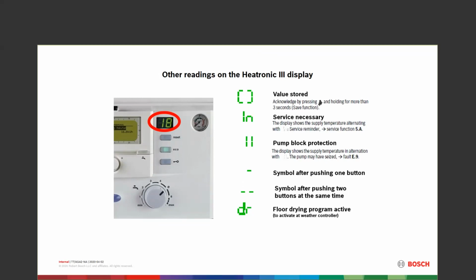The two other symbols, or two L's, I don't know what you want to call that one, we don't see very often. It's telling me that the pump might have seized. That's going to show up as a fault code E9. Usually E9 shows up before that pump block shows up. The single dash that you see there, you're going to see if you press a single button. The double dash if you press two buttons at the same time. I'll show you the reasons for that as we go in.